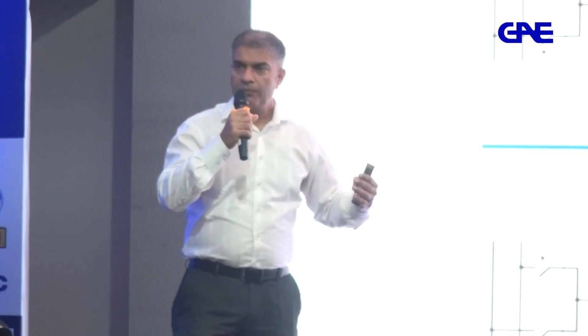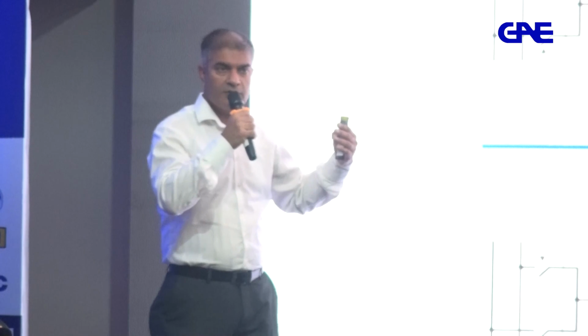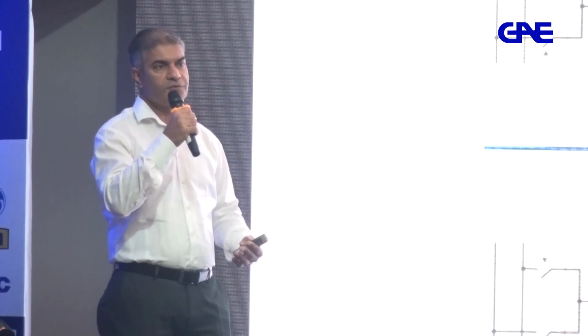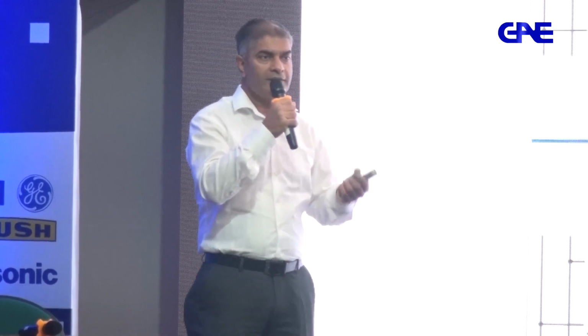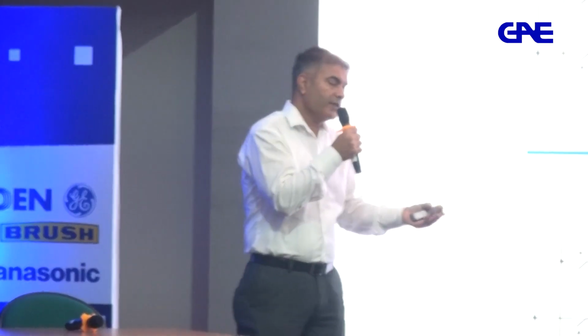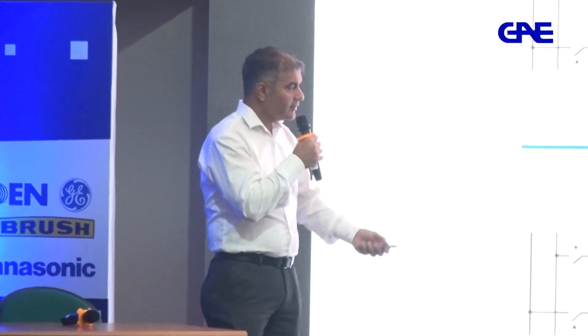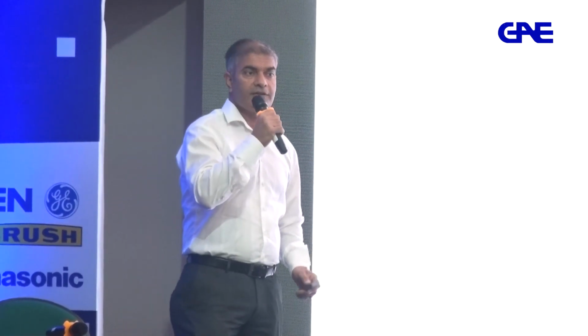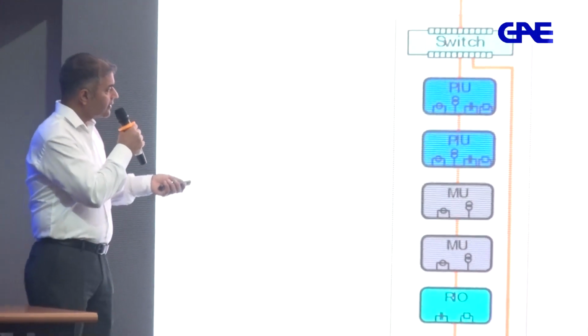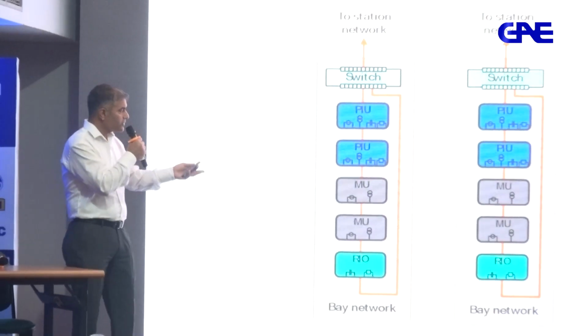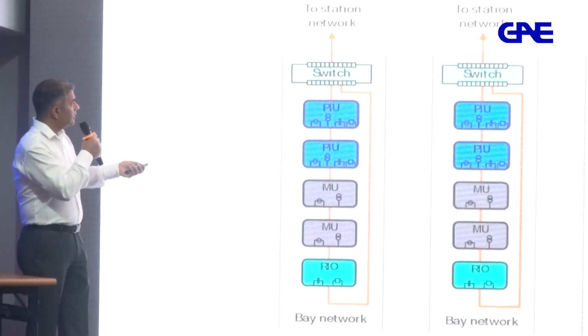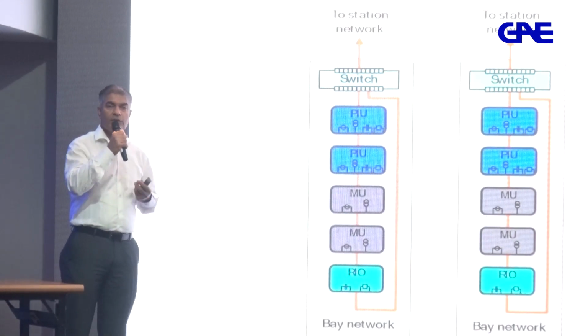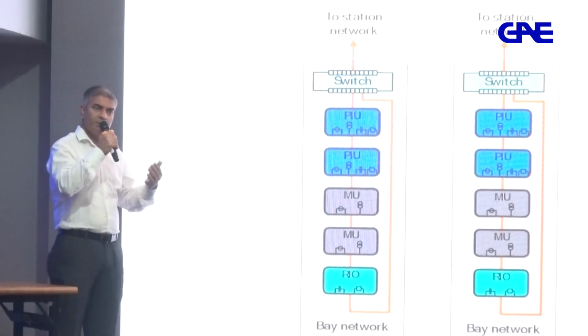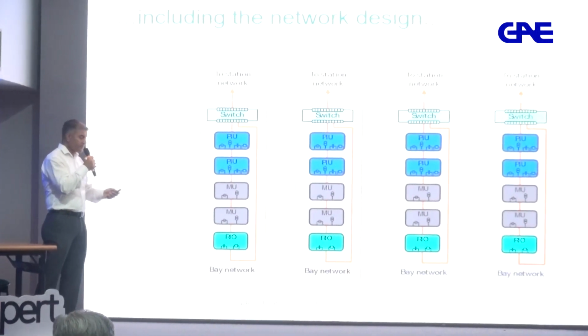So now you can imagine that if you apply this to a substation, your drawings, your AC and DC drawings, are considerably reduced, right? And it's standardized. When the maintenance guy, when your operator goes to the substation, he knows exactly what the wiring is, because he doesn't need to probably refer to the drawing, because he knows that everything is identical. So that's how you can bring the standardization, right? Similarly, the network design can be standardized, and the same sort of network connection to switches can be applied in a substation, right? The way you filter out your GOOSE messages and sample values, the data traffic, it can be standardized.